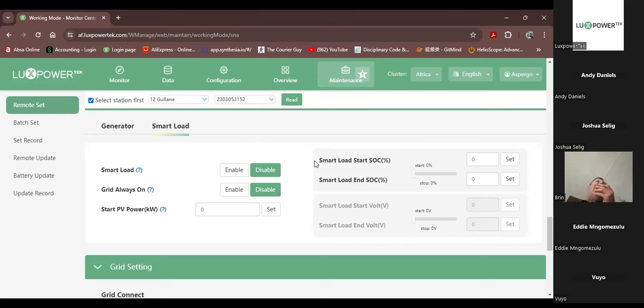But when the machine goes into off-grid mode, then it will look at these functions here. So it will want to know what the SOC of the battery is. You can say, for instance, let's make that 50%. Get it as close as I can. And I'm going to make that 90%.